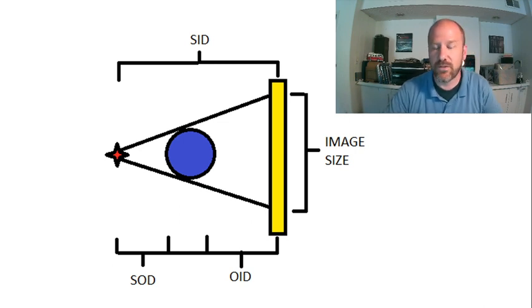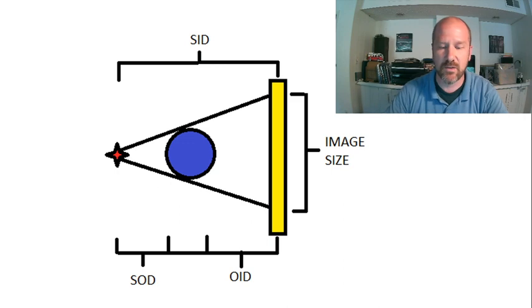But as you can see, with just keeping the SID the same, as we increase the OID, we would expect the image size to be magnified. And so we would call this a form of size distortion.